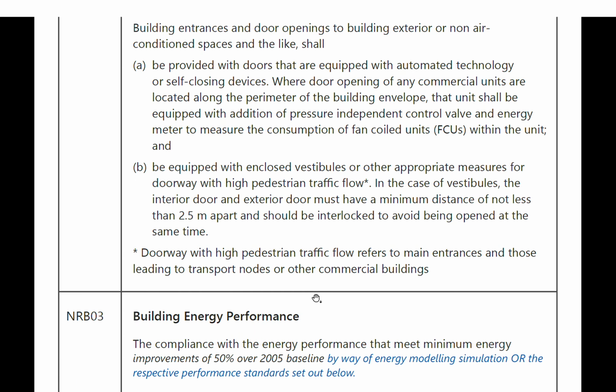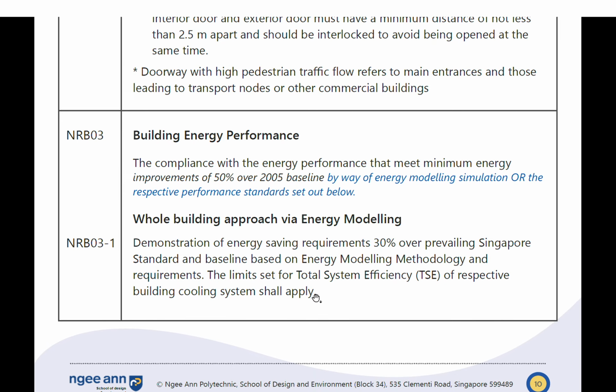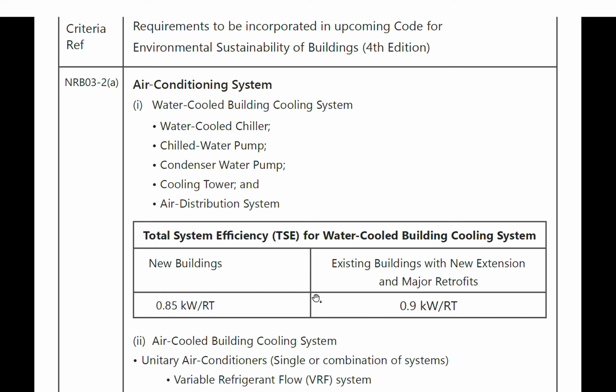Yeah. So energy performance, the compliance of energy performance, which means a minimum energy improvement of 50% over the baseline of 2005. So these are new buildings that we need to think of ways to model and reduce the energy performance. The whole building approach for energy modeling could actually be a part of it, and so we actually have something called TSE, total system efficiency, respective to the building cooling system, which shall apply to such building modeling.